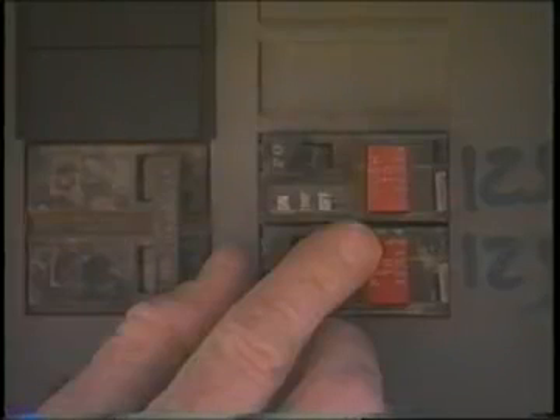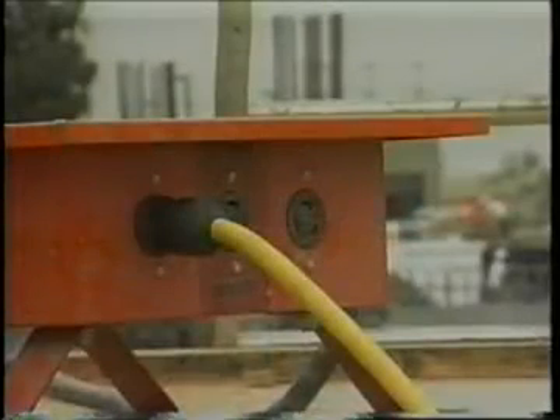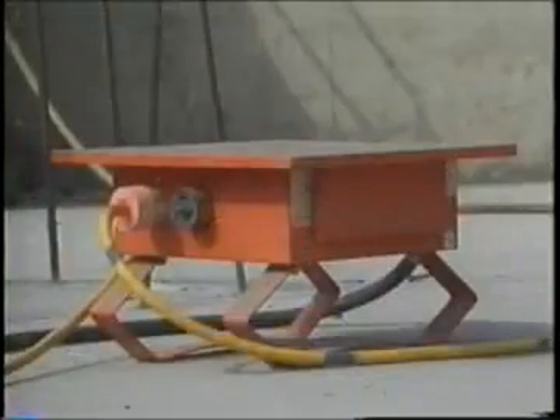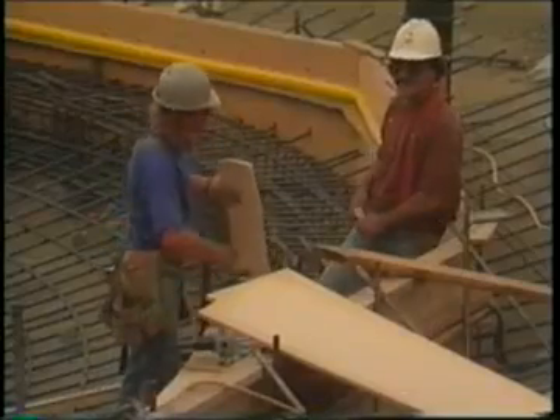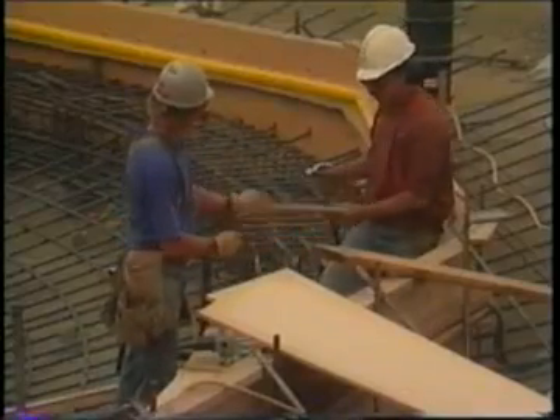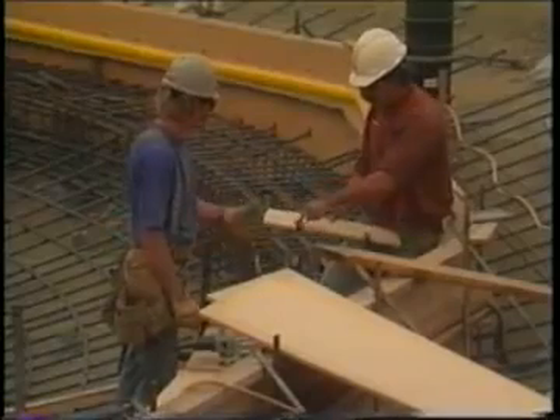Tripping of GFCIs, or the interruption of current flow, is sometimes caused by wet connectors and tools. It is a good practice to limit exposure of connectors and tools to excessive moisture by using watertight or sealable connectors. Providing more GFCIs or shorter circuits can prevent tripping caused by the cumulative leakage from several tools or by leakages from extremely long circuits.